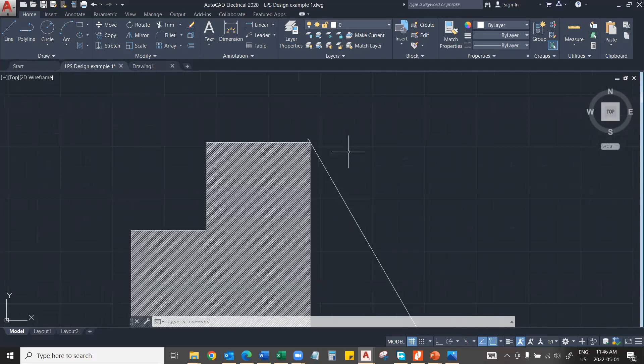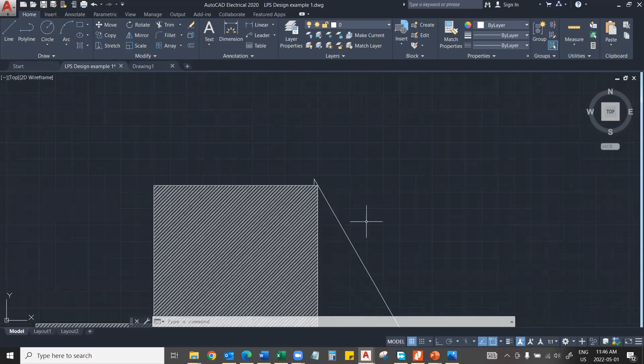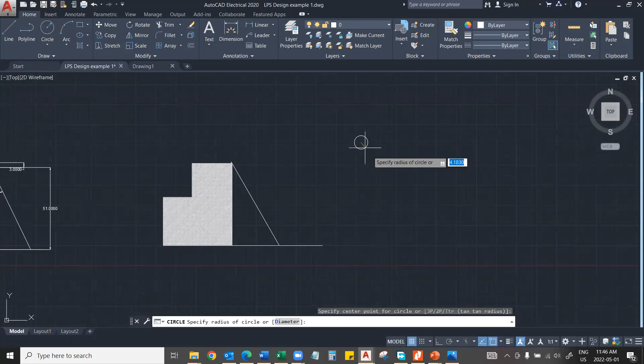If we are going to apply the rolling sphere method, this will be a great example for us. We considered a class 4 protection. So if we have a rolling sphere, the concept should be we have a sphere now in 2D, and the radius is 60 meters - we have a 60 meter radius.